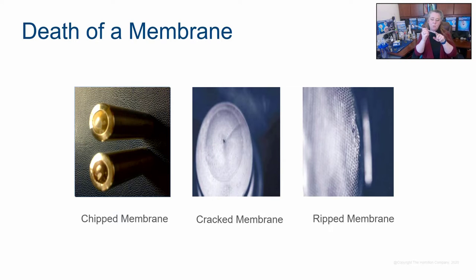And the liquid inside of a polarographic probe, what happens to liquid when it gets hot? It expands. And if you have a crack in your membrane, or if you overflow and you add too much liquid inside the polarographic probe, when you add heat and pressure, what happens? The liquid expands, but if there's too much liquid, the liquid has to go somewhere, and it does what's called a ripped membrane, and it bursts out of the end of the membrane and blows up. If you're lucky, it happens when you're in autoclavation or when you're in steam in place.